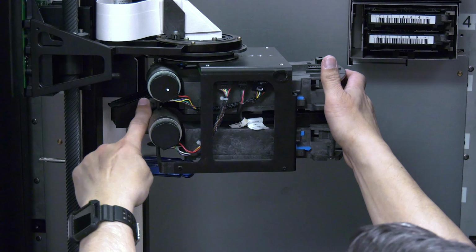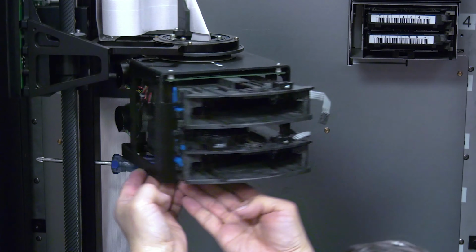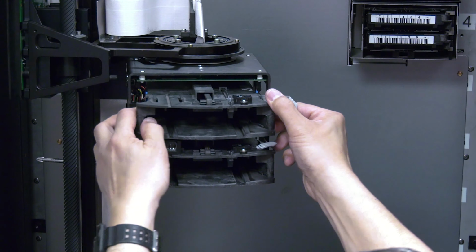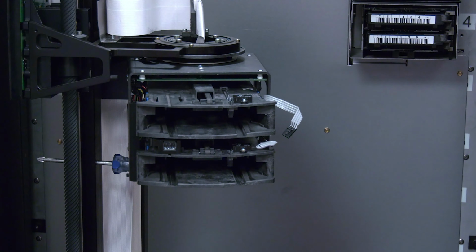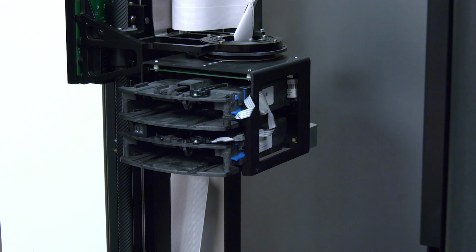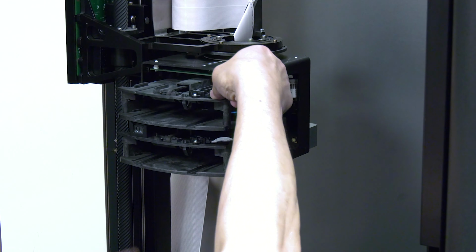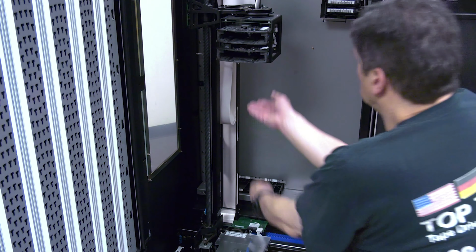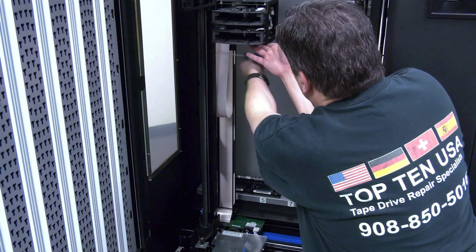You can then slide both blue slide locks forward to lock the gripper into the gripper cage. Check to ensure that the gripper is completely secure in the cage before proceeding. Now you can plug in both the front sensor and the motor to the top gripper and ensure all cables are routed correctly.